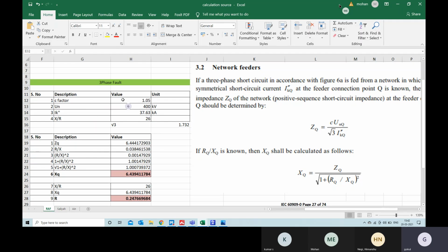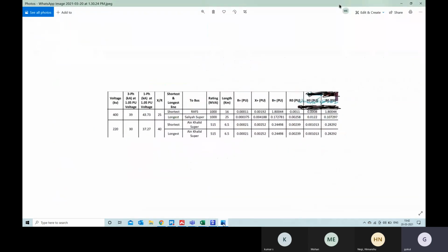So this C factor is 1.05, and I can show you the reference. Here they have said 1.05 per unit. Generally, if there is a fault, there will be two voltages: the pre-fault voltage and the post-fault voltage. What they are trying to say is that when there is a fault, there is a chance my system will be at 420 kV, which is 400 kV plus 5%. The 39 kA they have assumed is the fault current when my system is at 420 kV. Similarly here, when the system is at 420 kV and there is a single line to ground fault, the maximum fault current is 43.73 kA. Do you have any doubt up to this? No, it's clear.